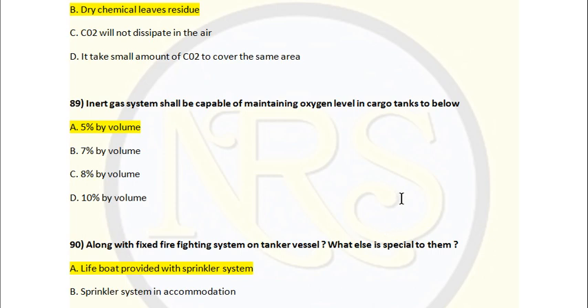The maximum allowable oxygen content inside the tank is 8% as per ISGOTT and SOLAS. As per SOLAS requirement, it is not more than 8%, but the alarm should activate at a percentage of 5.